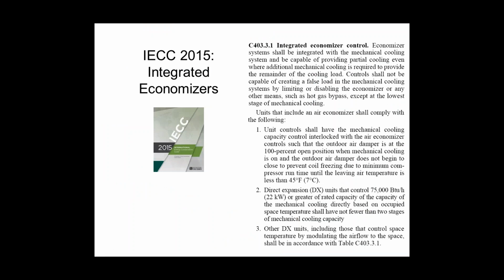Which means that no matter what, you have to have a two-stage thermostat. Even if you have a one-stage DX system, you need to have a two-stage stat. That is a dead requirement to make this actually work. There are a few other things listed in the integrated economizer section that have nothing to do with economizers, such as note number 2 and number 3 below. So we will come back to those later on. Why they're in the economizer section, I have no idea, but nonetheless, we'll come back to those in a few minutes here.